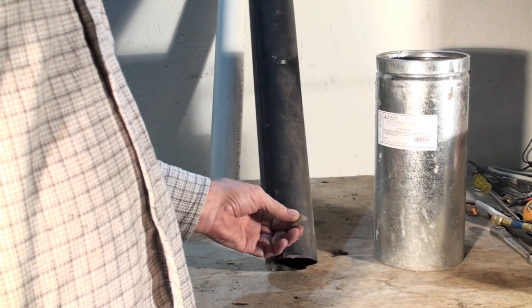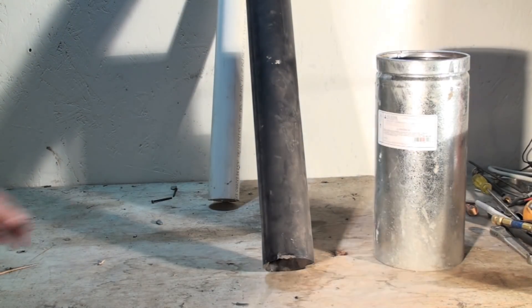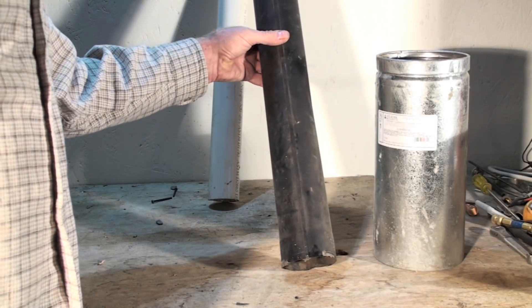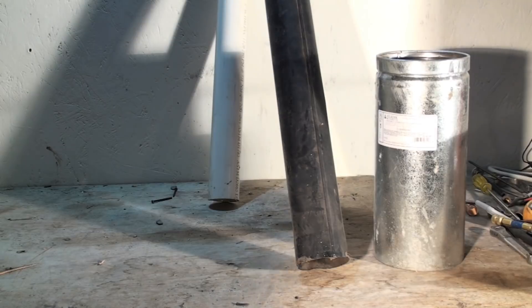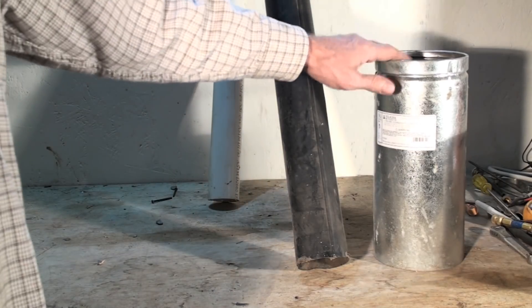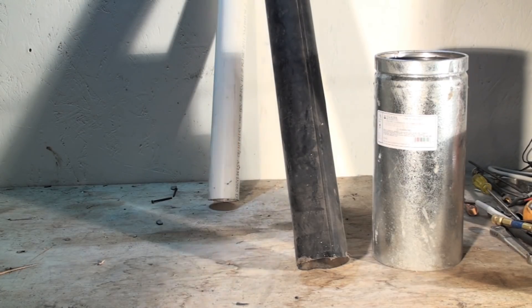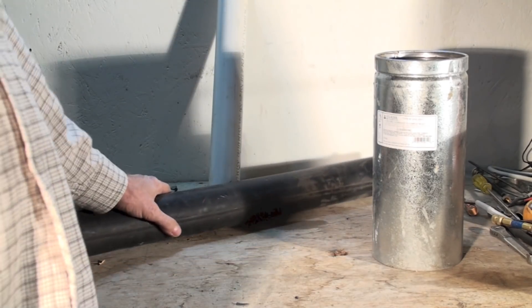Look close, you can see we sealed this with silicone to keep it from leaking. We put a little silicone bead along here. That was a colossal failure. These were high efficiency furnaces they were on. We got rid of this type of vent because it could not handle the condensation in it. We used this for a little while. Some guys used Plex Vent on some. That's a brand name. Recalled. Terrible, terrible mess. Good grief what a mess that stuff was. Got rid of most of that.